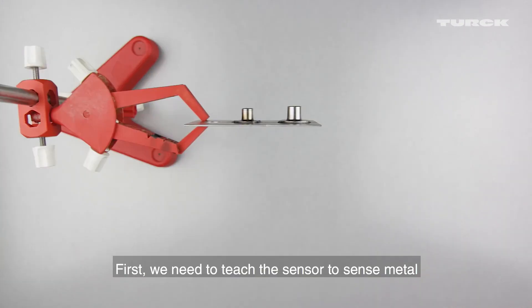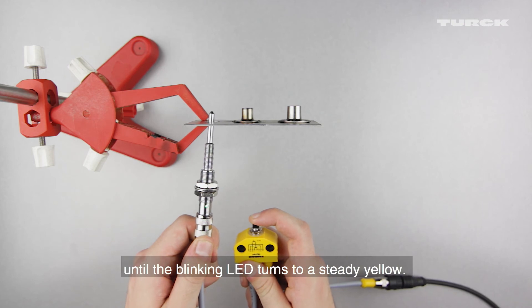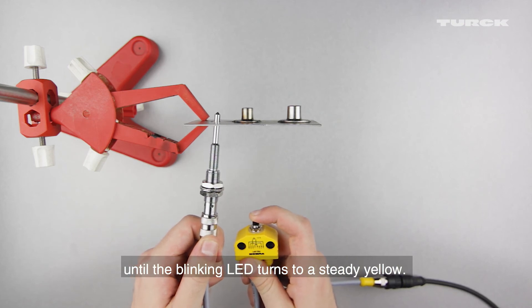First, we need to teach the sensor to sense metal without the nut in place. To do this, insert the sensor through the mounting hole. Press the button of the teach adapter until the blinking LED turns to a steady yellow.